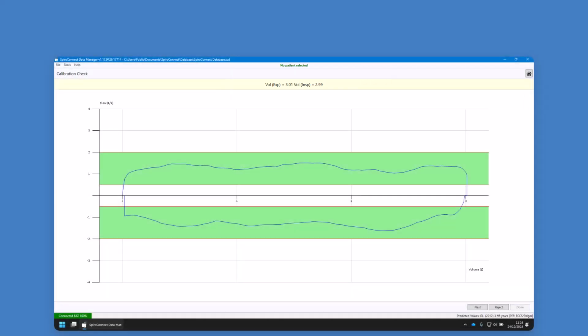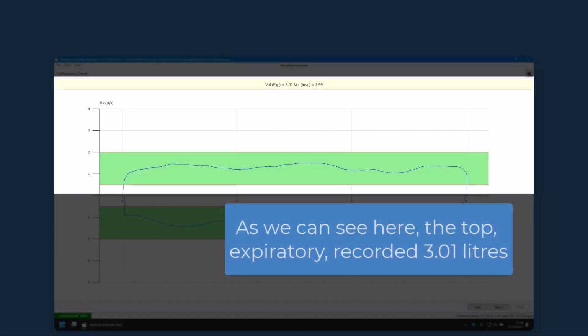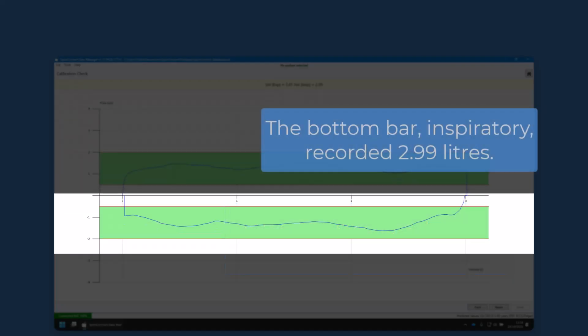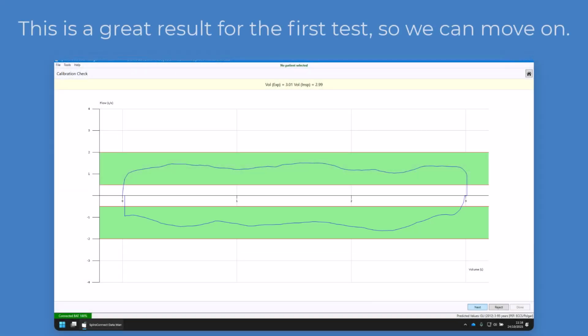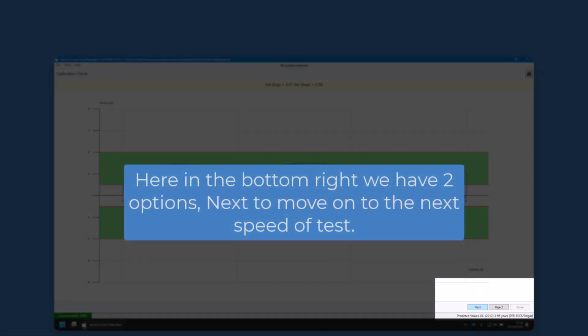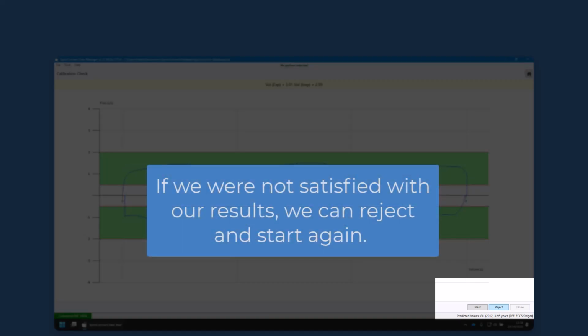The message at the top of the screen will change to show the results of the first test. As we can see here, the top, expiratory, recorded 3.01 liters. The bottom bar, inspiratory, recorded 2.99 liters. This is a great result for the first test, so we can move on. Here in the bottom right we have 2 options. Next, to move on to the next speed of test. If we were not satisfied with our results, we can reject and start again.